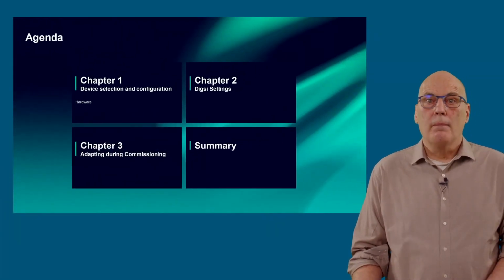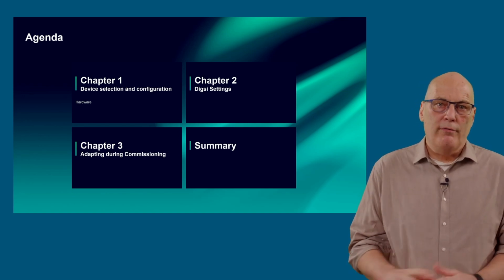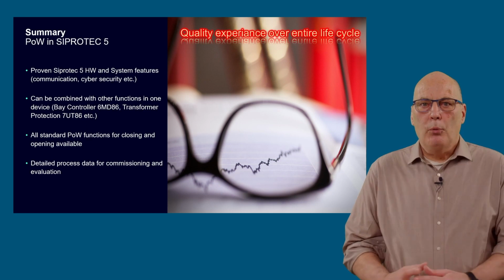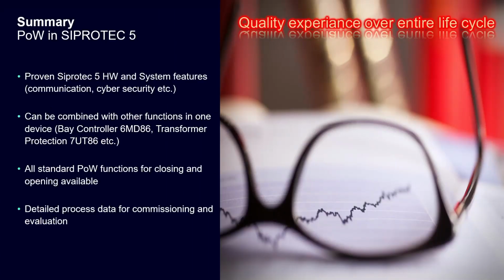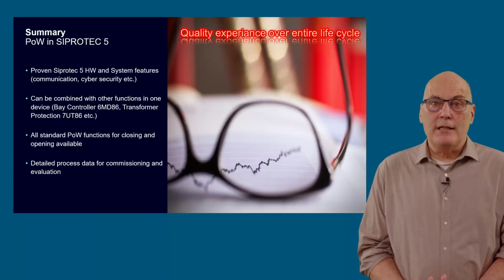This brings us to the end, at which point I would like to summarize with the following single slide. The point-on-wave function in SIPROTEC 5 has the following advantages. The user profits from the proven and standardized hardware of SIPROTEC 5 as well as the system features, for example, communication protocols, cybersecurity, and so on. The point-on-wave function can be combined with other functions in the same device, for example, a bay controller or transformer protection. All the standard point-on-wave functions and features for closing and opening are included. Detailed process data, the fault log as shown earlier, is provided for clear and defined analysis and adaptation during commissioning and service. This ensures a quality experience over the entire life cycle.